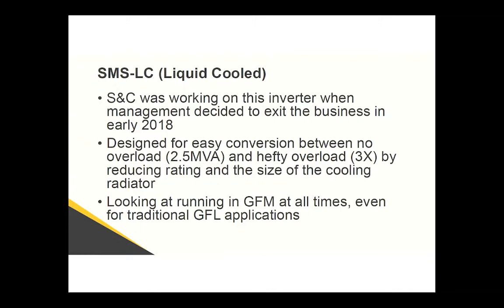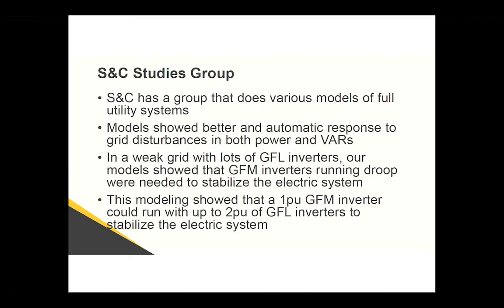Our last development was an SMS liquid cooled inverter. One of the things we liked about the liquid cooling was we could optimize it for power without overload, which was what we were doing initially, but we could also reduce the cooling system and have a lot more overload if we wanted to handle systems that needed more overload. And we're looking at, can we run in the grid forming mode all the time and still meet the existing standards? So that's what we're pushing toward. But unfortunately, our company made the decision to let us get out of the inverter business. So we stopped working on that.